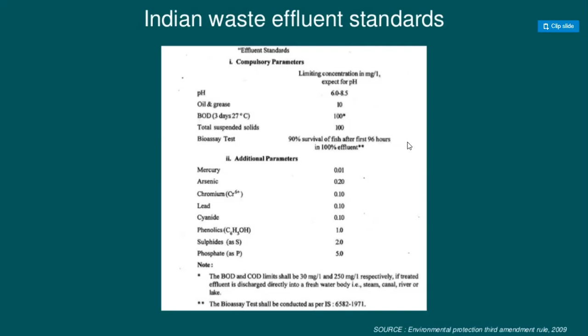Indian waste effluent standards. Compulsory parameters: limiting pH is 6.0 to 8.5, oil and grease 10, BOD, biological oxygen demand, 3 days at 27 degrees centigrade, limit is 100, total suspended solids 100. Bioassay test: 90% survival of fish after 96 hours in 100% effluent. Additional parameters: mercury 0.01, arsenic 0.20, chromium 0.10, lead 0.10, cyanide 0.10, phenols 1.0, sulphides 2.0, and phosphate as P 5. The BOD and COD limits shall be 30 milligram per liter and 250 milligram per liter respectively. If treated effluent is discharged directly into a freshwater body, that is a stream, canal, river, or lake, the bioassay test shall be conducted as per Indian standards.